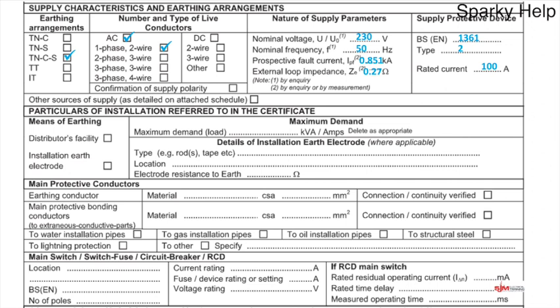If we carry on working our way down, we can see we've got supply polarity. Now, if we've got all of these things up here, the chances are our supply polarity was okay if you carried out a fault loop impedance and prospective fault current test, because the meters generally have polarity built into them. So we can tick that one. Other sources of supply, as detailed on attached schedule. So other sources of supply, if you've got a wind turbine or solar panels or generators or anything else like that powering back into your system or into the grid, probably both. But if we haven't, then it's either an N/A or just leave it blank. I tend to leave it blank.